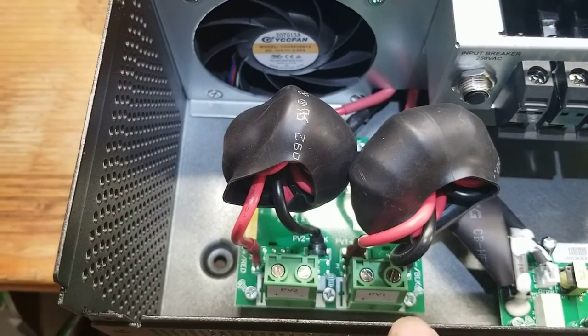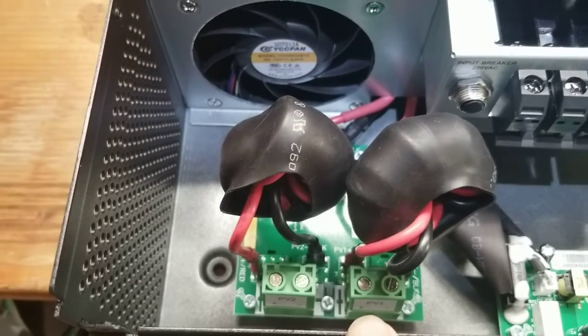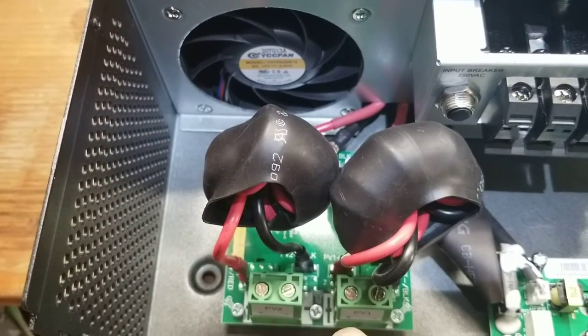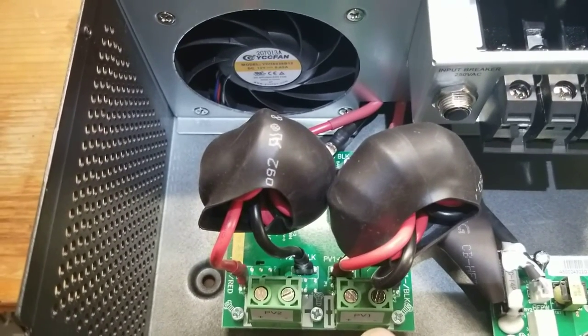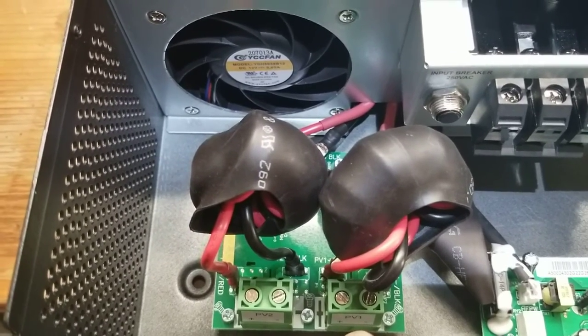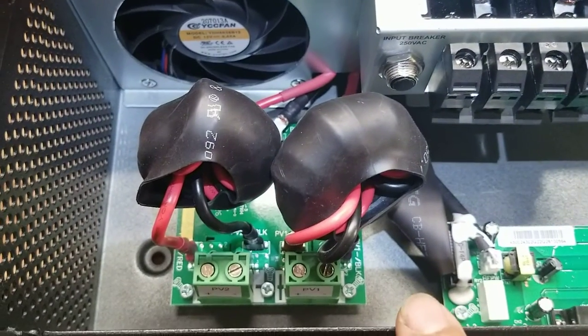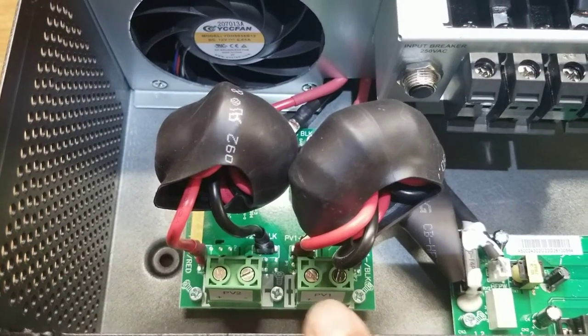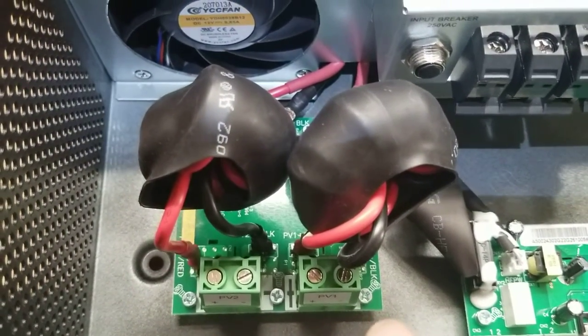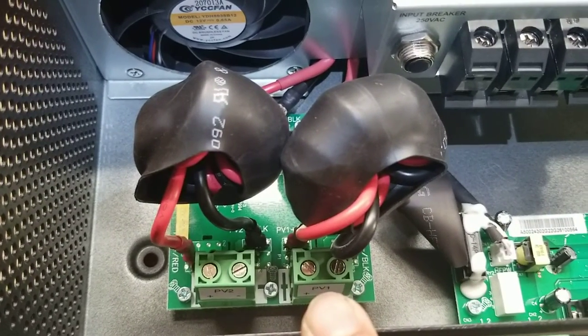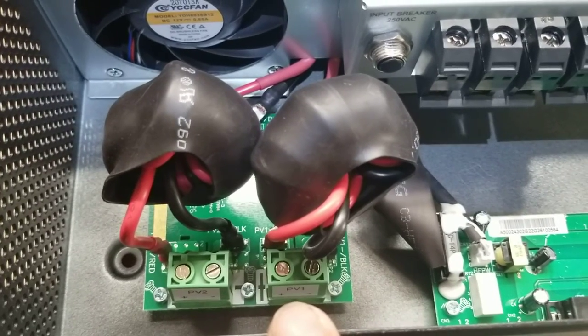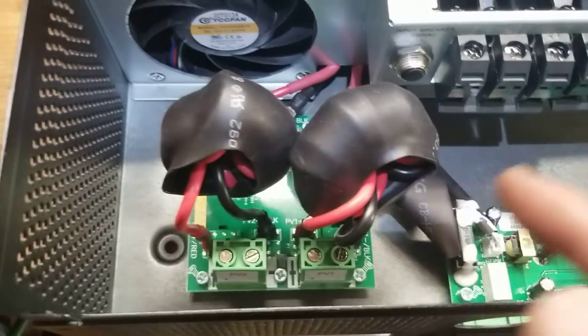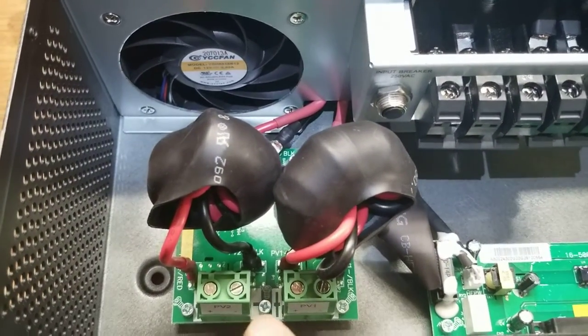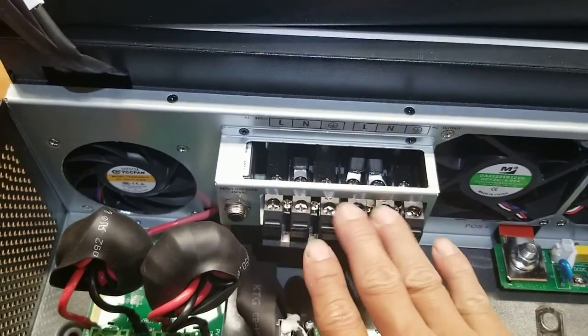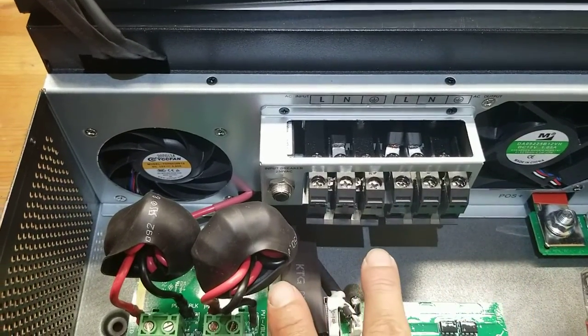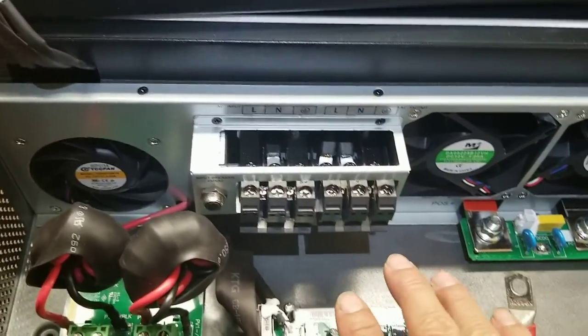Make sure you check the open circuit voltage before you connect anything. The total voltage must be less than 500 volts DC from the panels, otherwise it's bad for your unit. Open circuit means the PV hasn't been connected to anything yet. Add up the voltages together - it must be less than 500 volts to protect your unit and your investment. Don't go over it thinking it will drop down once connected. That's dangerous and a bad idea.